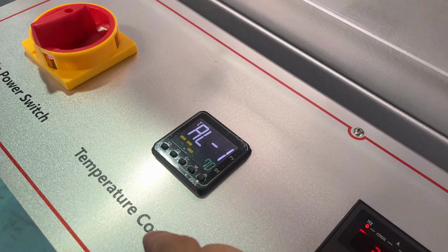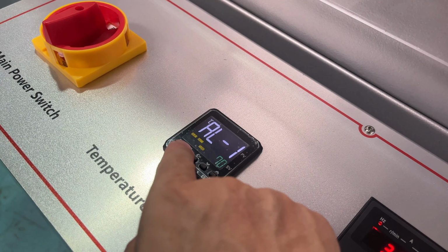In this system, we mainly use two important protection parameters, AL1 and AL2. AL1 is set to 70 degrees Celsius. This parameter is used as a cooling stop condition during shutdown. When the machine is stopped using the stop button, the heating function will turn off and the temperature will gradually decrease. During this cooling process, the conveyor will continue running. Once the temperature drops below 70 C, the conveyor will stop automatically, and the machine will enter a fully idle and safe state.